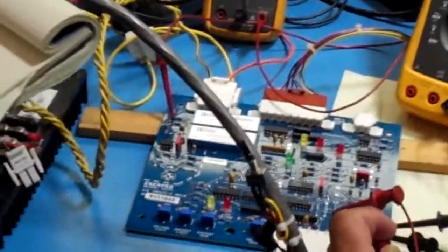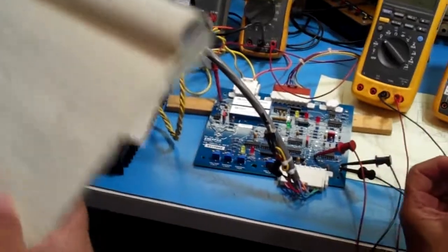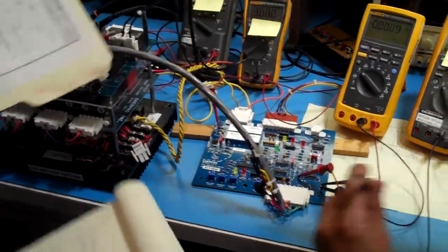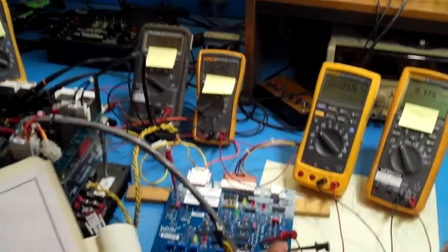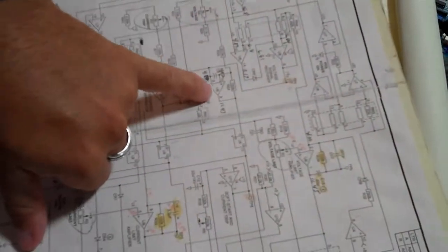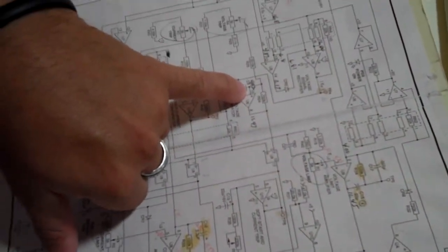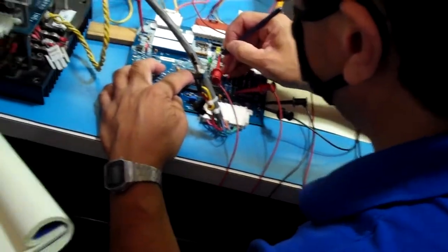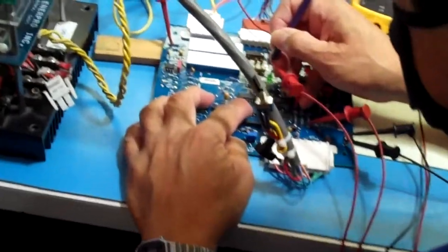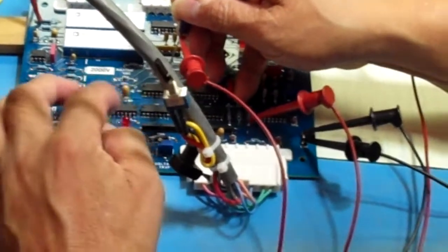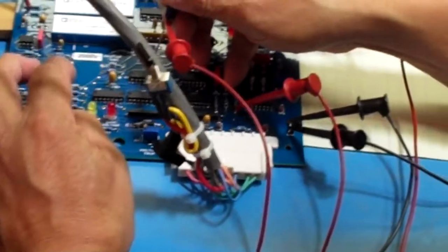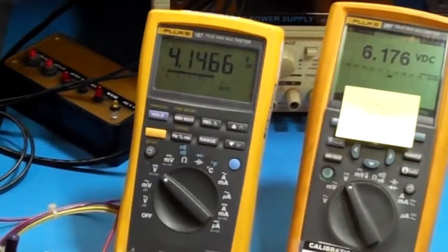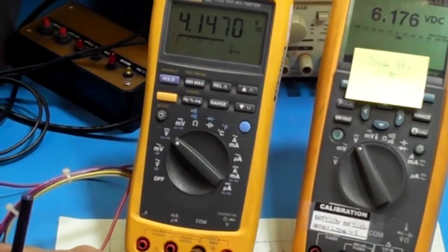Now, according to this circuit, let's concentrate first of all on the voltage. The 3.88, which is coming here at test point 4. And I'm going to ask Tony to look at U6 position 10, because that is my voltage trip. Okay, under normal conditions, for everything to be working okay, that threshold is above the feedback of 3.86.